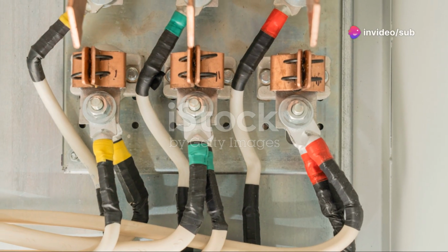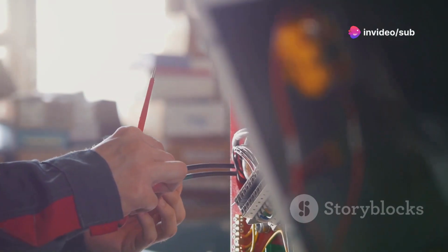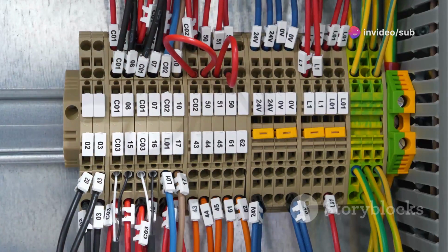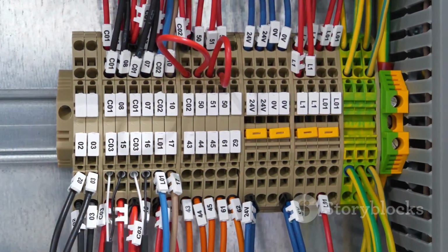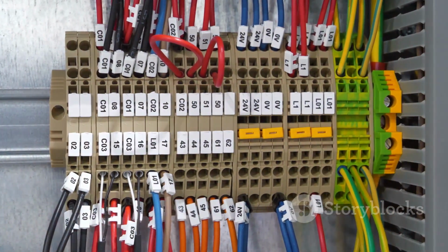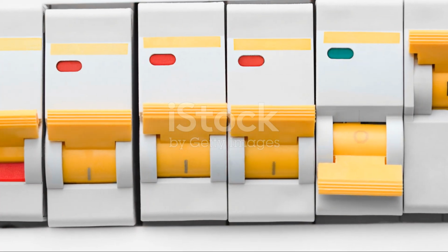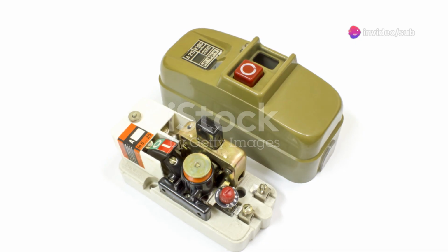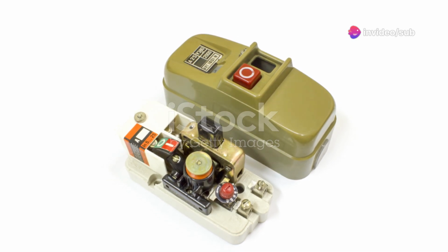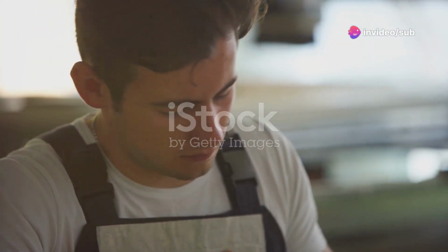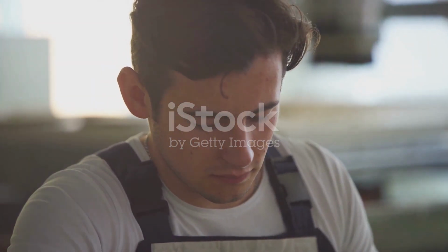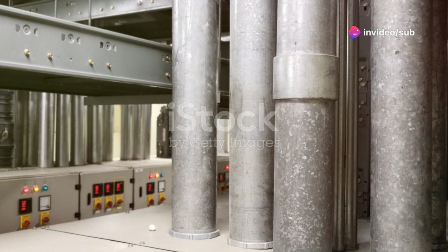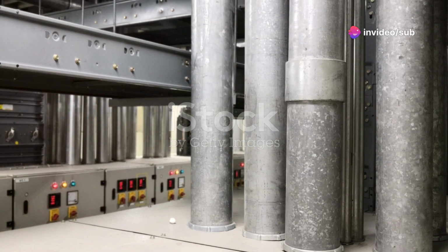Sometimes it's for connecting extra circuits, sometimes for making bus bar connections easier. The key thing to remember is that these terminals are tested and rated for the job. If you follow the manufacturer's instructions, they are just as safe and reliable as a single terminal breaker. You're not cheating or breaking any rules by using them as intended. If you've ever felt unsure about using all the terminals, just relax. As long as you respect the guidelines, multiple terminals are there to help, not to confuse.